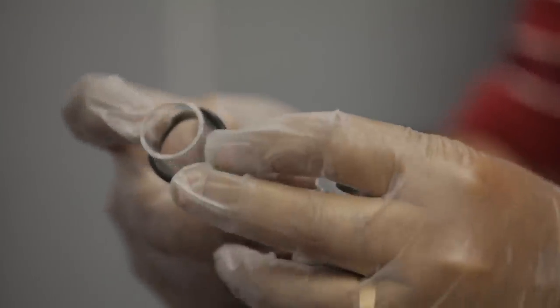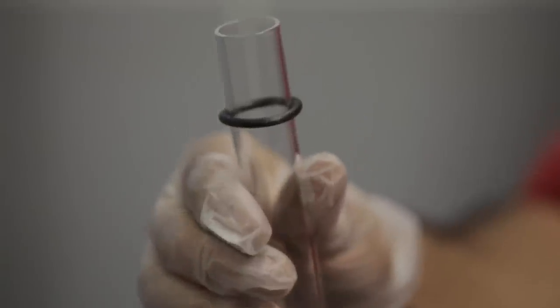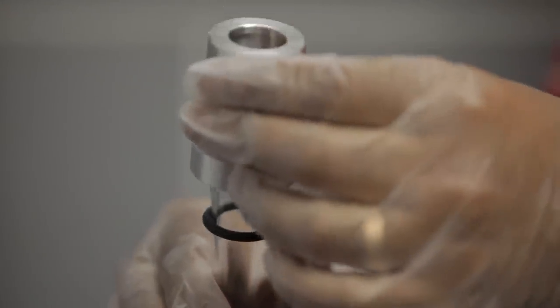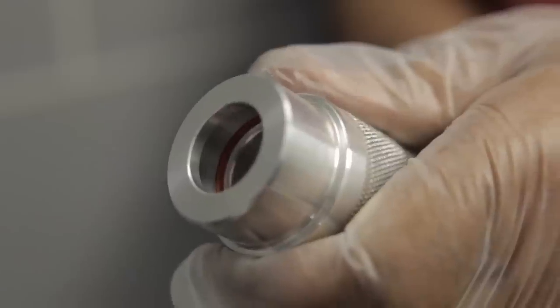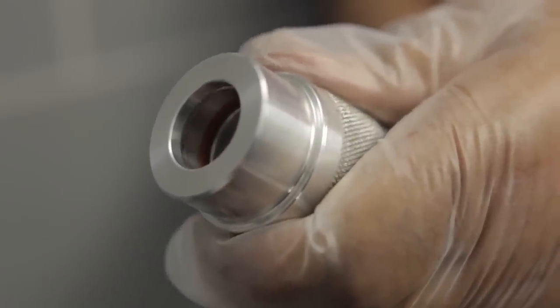Gently slide the dome O-ring over the open end of the quartz dome to about 1 inch from the open end. Slide the open end of the dome into the gland nut. Make sure that the end of the dome goes past the O-ring and touches the end of the nut.